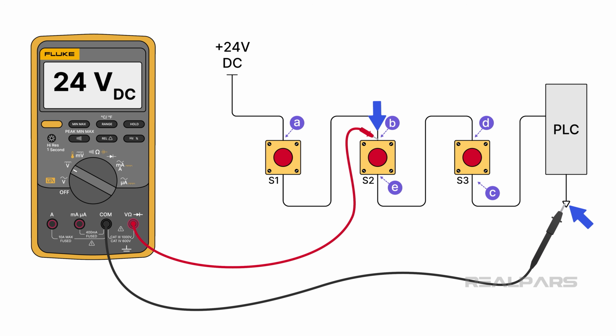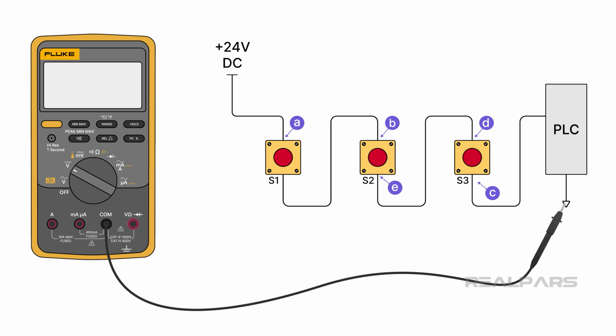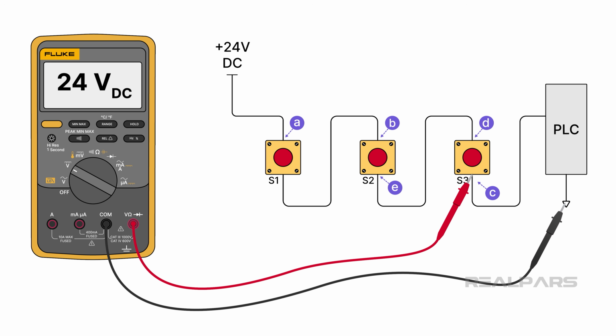If you measure 24 volts DC, everything up to and including S1 is fine. Let's split the circuit in half again and place the red probe on point C. If you measure 24 volts DC, it proves that S2, S3, and the associated wiring are fine. Let's assume you measure 0 volts DC. Aha! That reading indicates an open circuit between points B and C.